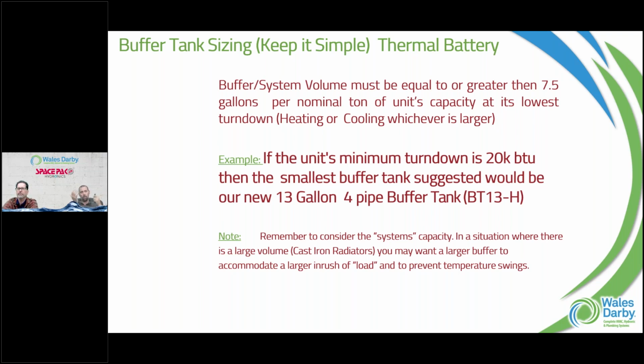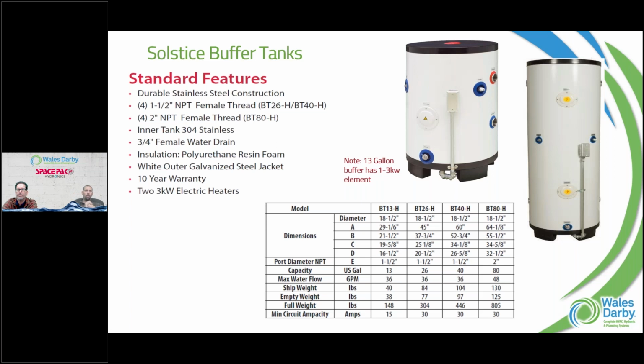That would put us right in the market for that 13-gallon buffer tank, which was something I don't think we've had, right? That was an introduction really when the inverters came out. It was a fairly new introduction, yeah. So buffer tanks, again, just think of it as a battery, right? There's not too much to it. It looks like a regular electric water heater, but a couple different configurations. As you saw in some of the diagrams, everything that we had there was all 4-pipe, we call it, right? So 2 pipes from the outdoor unit, 2 pipes out to the indoor system, so whatever's hooked up to that.